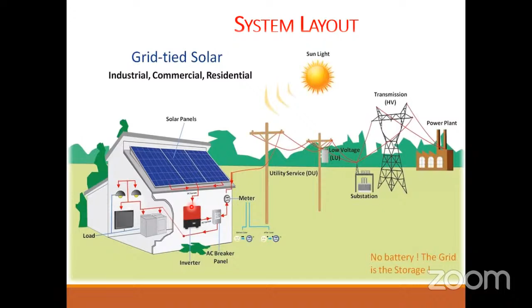So this is the basic layout. Here I'm not going to consider any storage, because the consideration is my grid will behave as a sink and source for me. It means that whenever the generated power, whatever source you use, maybe solar or wind, if your power is more than your local demand, the extra power you will feed inside the grid, and that time the grid will behave like a sink. Same time, when the generated power is less than your local load demand, then you can take the extra power from the grid and fulfill the load demands. So that time the grid will behave like a source. So this sink and source behavior I consider with the grid, and this is the consideration.